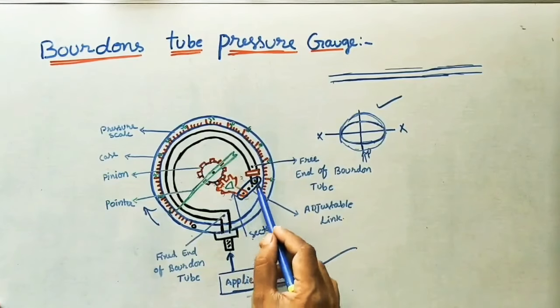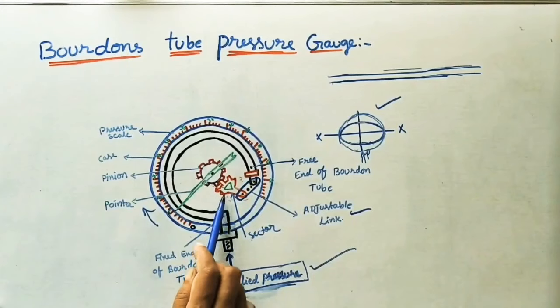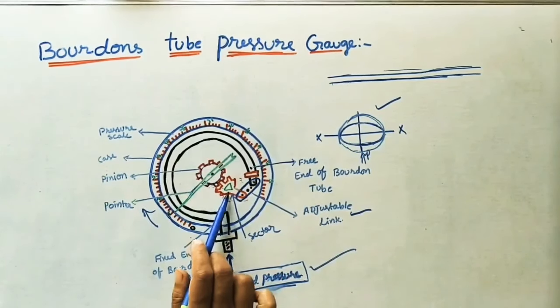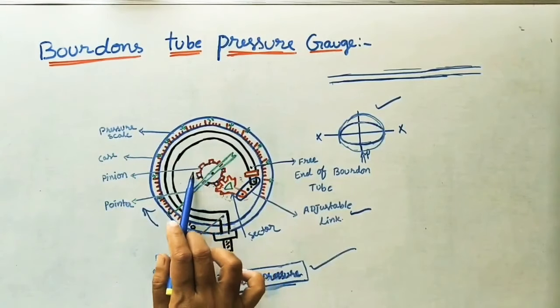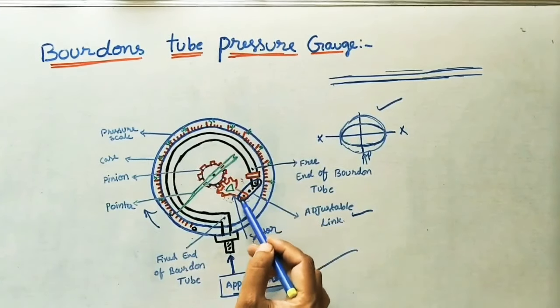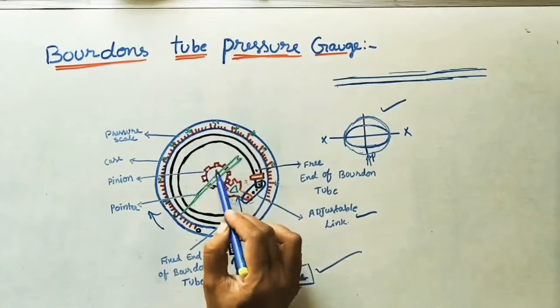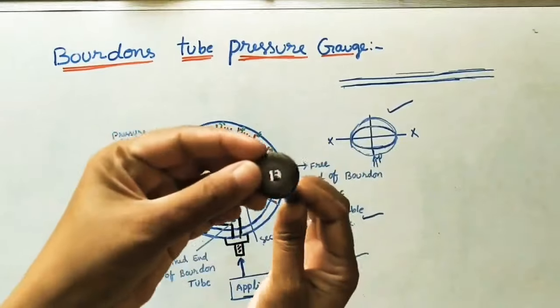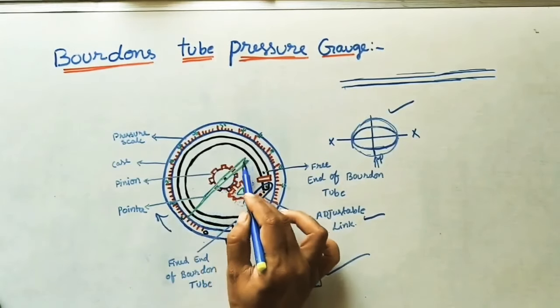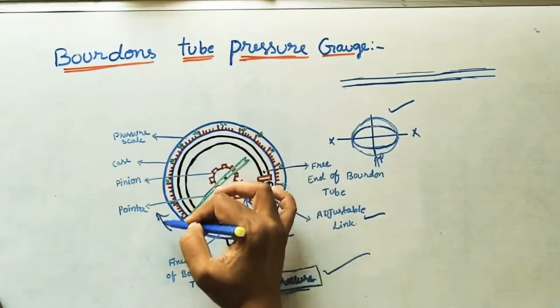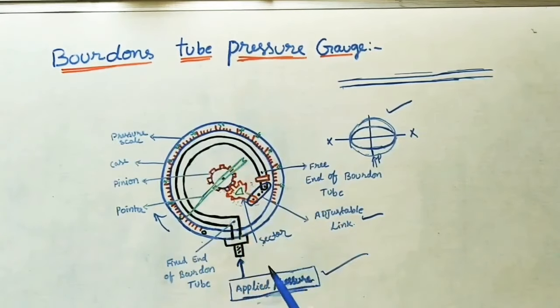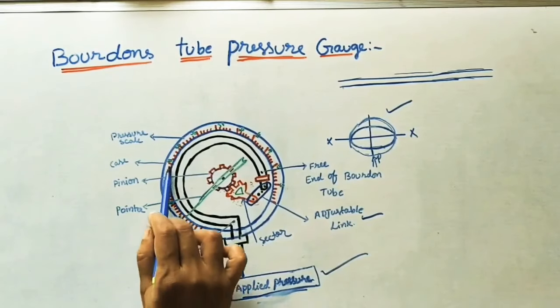The other end of the Bourdon tube is the free end. This free end is connected to an adjustable link, which is in turn connected to a sector and pinion arrangement. The sector is one-fourth of a circle with teeth on its surface; these teeth coincide with the teeth of the pinion. When the adjustable link moves, the sector moves, rotating the pinion, which is connected to a shaft. The shaft rotates a pointer over a circular scale marked with values such as 5, 10, 15, 20, 25 in bar or newton per meter square.